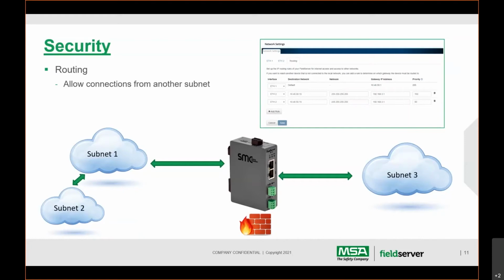Now with routing, you can configure Ethernet 1 to listen here, say, I've got devices on subnet 1, which is great, I can get to. But now you point the FieldServer towards the router between subnet 1 and subnet 2. That's done in the configuration page, as we've shown here, and you can get to those devices. So essentially, the FieldServer bridge could be polling devices on subnet 1 and subnet 2, and then doing the protocol translation onto subnet 3.